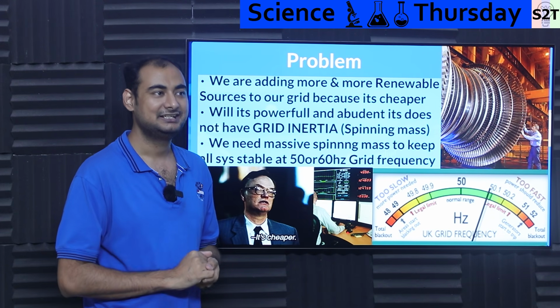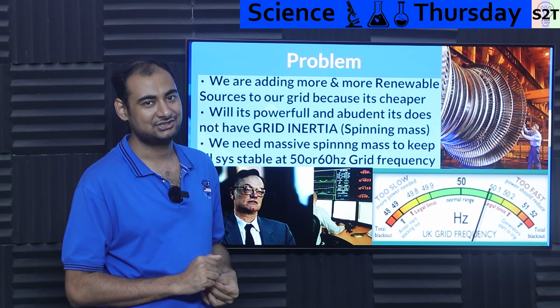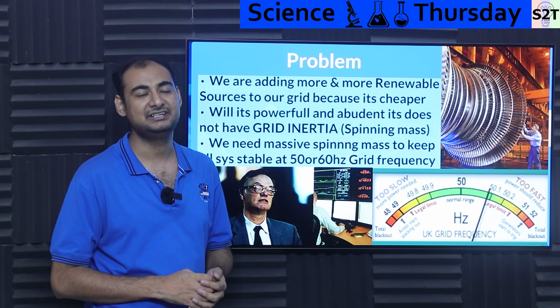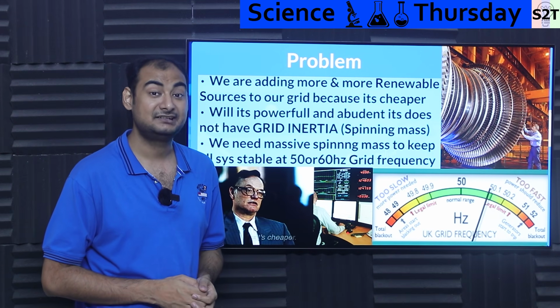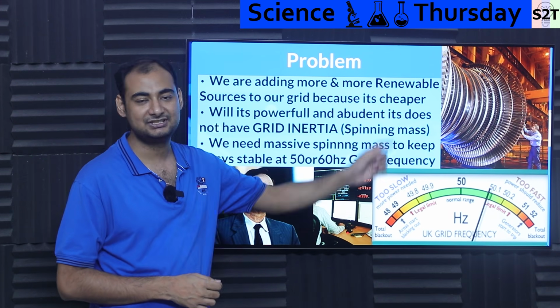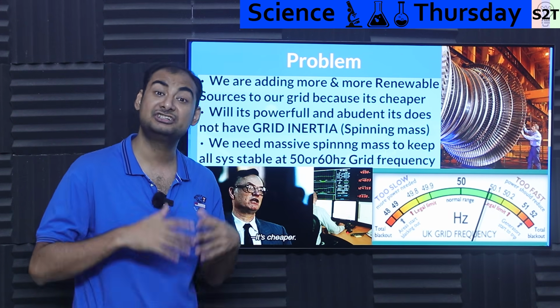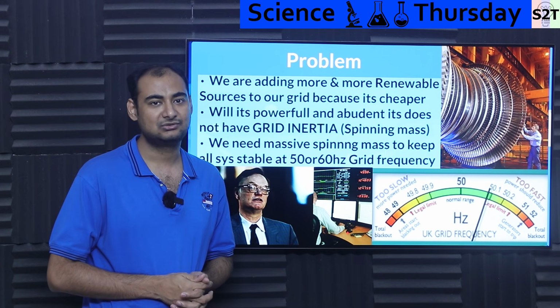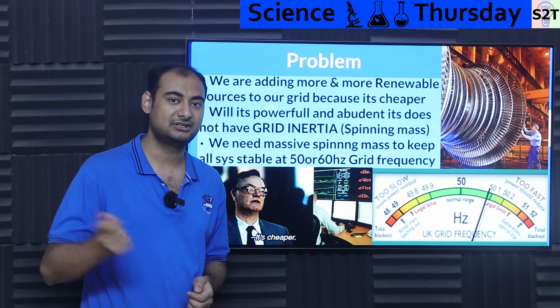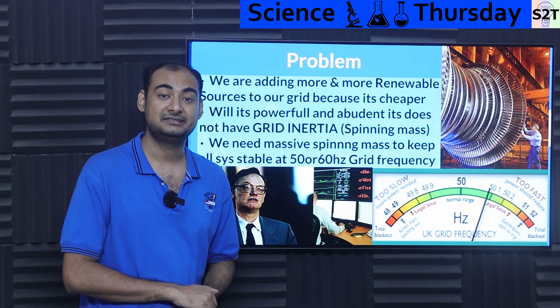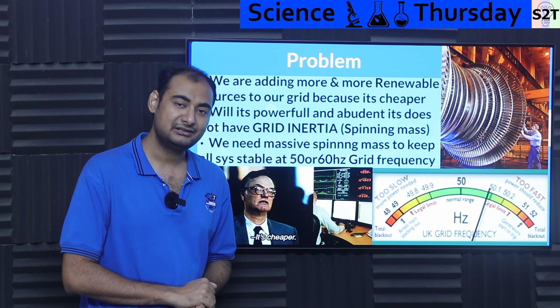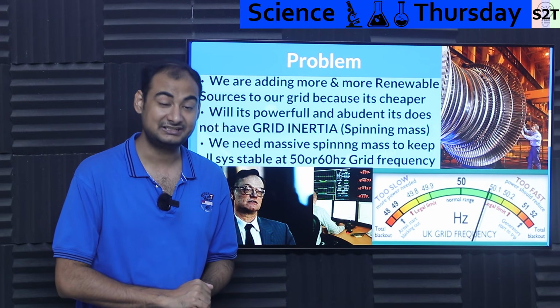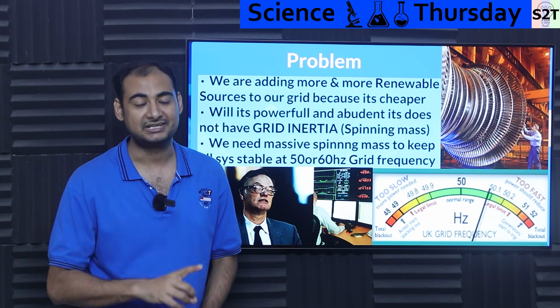But here's the funny thing: ironically, because our early technologies weren't that efficient, we had to make them very heavy, so it takes time to slow down. For example, if this were rotating at 1500 rpm or 3000 rpm, it's not going to go from 3000 rpm to 0 rpm just because you dumped 100 megawatts of load. It will take time to slow down. How much time? Enough for the control mechanism to detect what's happening and react to it.